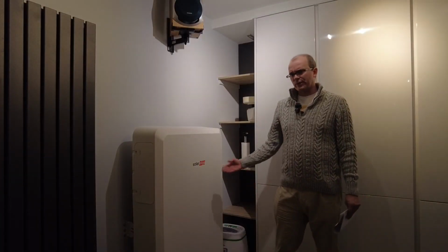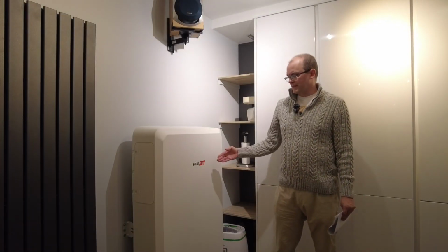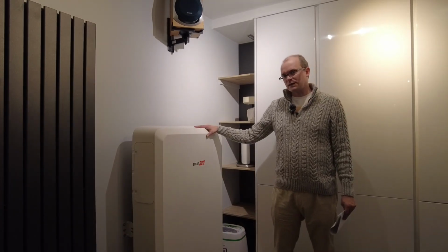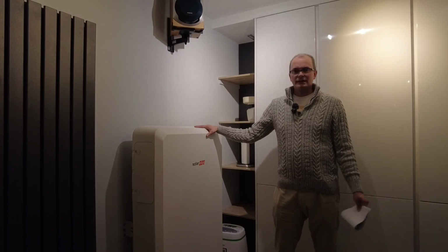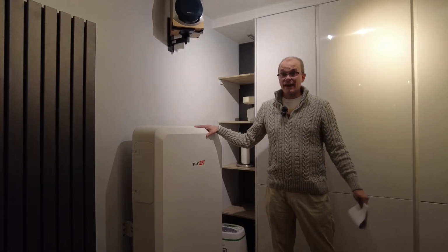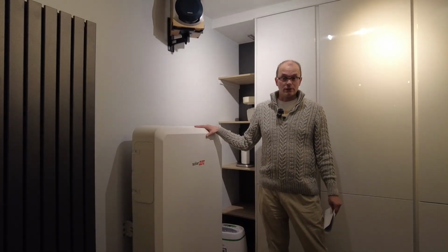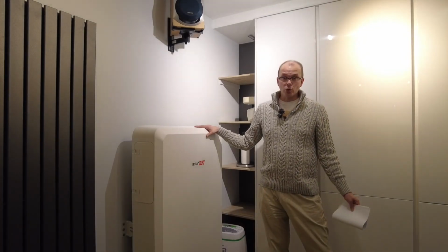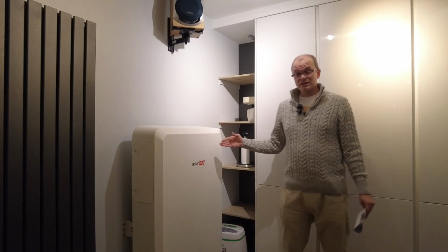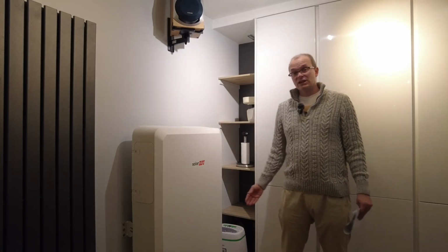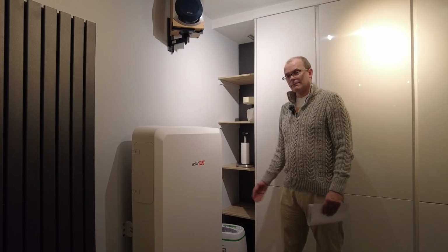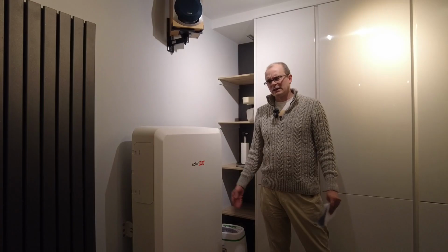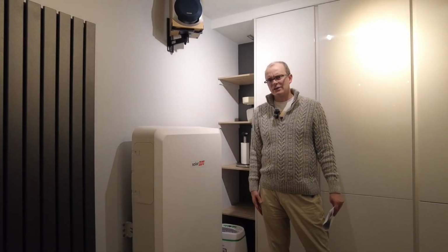Now, people who watched my previous video will know that I made an observation where I calculated that the efficiency of this energy bank was only 75%. Now, I reported that to Solaredge and they had also watched my video and they said that my calculation method was very interesting. But they reassured me and they told me that the efficiency of this was actually 90%. They pointed out a few flaws in my calculation method. So we're going to go into the figures and we're going to take a closer look.